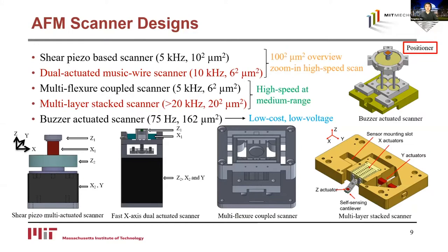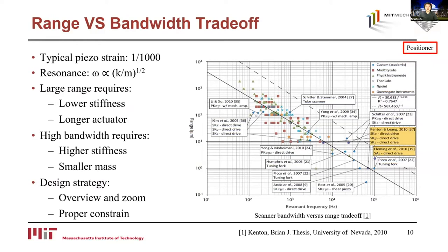AFM nanopositioner design is the key to enabling versatile imaging. The fundamental limitation in scanner design is the range-and-bandwidth trade-off. To realize a large scan range, lower stiffness and longer actuators — and therefore larger mass — are needed. However, to achieve high bandwidths, higher stiffness and smaller mass are required. This is illustrated in a log-log plot of bandwidth versus range for a number of scanners from the literature. To overcome this challenge, two approaches can be taken: the overview-and-zoom method using multi-actuation, and properly constraining the piezo actuators so that unwanted resonance modes are not excited.